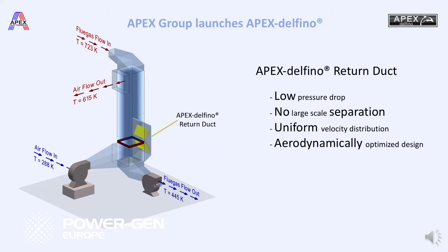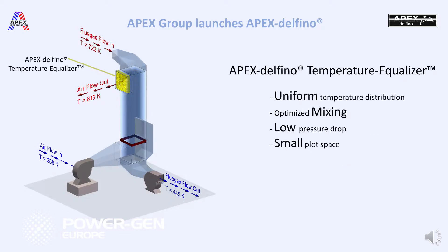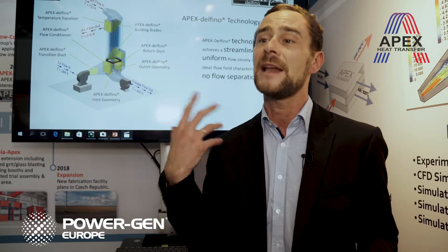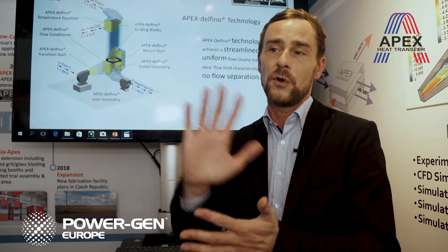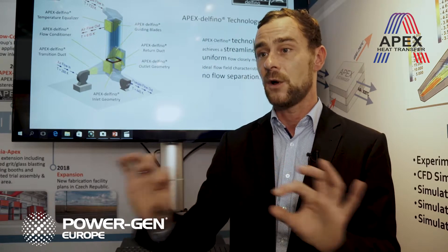This is achieved by aerodynamically optimizing the whole fluid path through the heat exchanger. We achieve that target by extensive laser optical measurement techniques — specifically particle image velocimetry and laser Doppler anemometry. The laser Doppler anemometry is a laser optical point-wise measurement technique with the highest accuracy currently available in the market, used for example by the German weather forecast to calibrate their anemometers. With the particle image velocimetry system, we get a very good overview of coherent flow structures, so we can detect single vortices in our duct or channel and optimize the flow distribution.